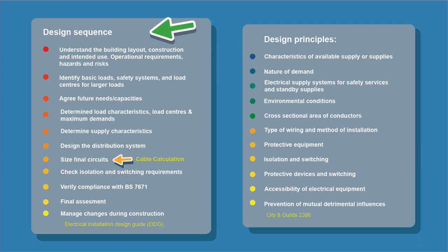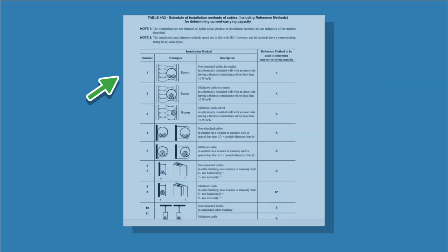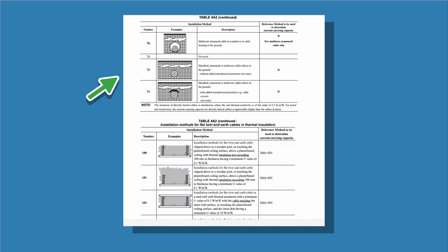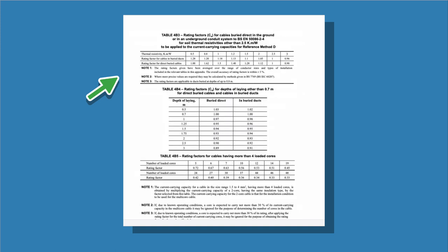For method of installation, we have our design sequence and design principles — we'll come back to this later. We're sizing our final circuits and finding the cross-sectional area of the conductors needed. For this example: it's an EV charger, the circuit length is 25 metres, it's clipped direct, going through a high temperature section — that could be a conservatory, loft, or boiler room — and we're using twin-and-earth cable because it's all internal. We look in Appendix 4 of BS 7671, which has all our reference methods, installation methods, correction factors, and ambient temperature tables — essential for our calculations.